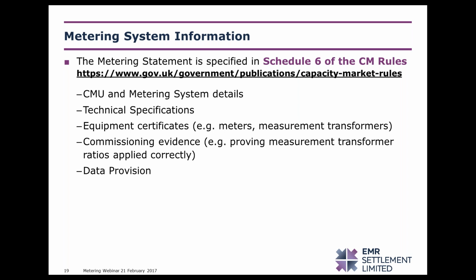Essentially, the purpose of the metering statement is to provide details about the configuration of the capacity market unit and the metering system, technical specifications of any metering equipment, certificates to prove the accuracy of the metering equipment, and evidence of commissioning to prove that the installed metering system is operating correctly and is measuring primary energy accurately. It will also confirm the method that data is provided to EMRS, either through a data collector or directly through a submission of a CSV file.